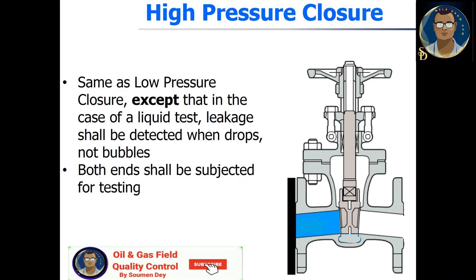High pressure closure: same as low pressure closure, except that in the case of a liquid test, leakage shall be detected by drops, not bubbles. Both ends shall be subjected for testing.